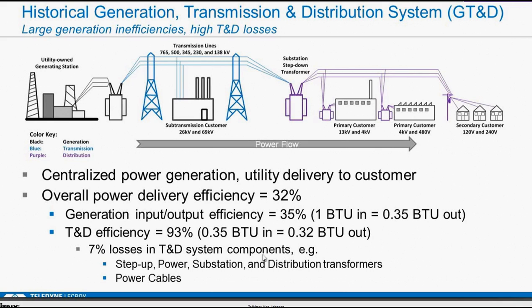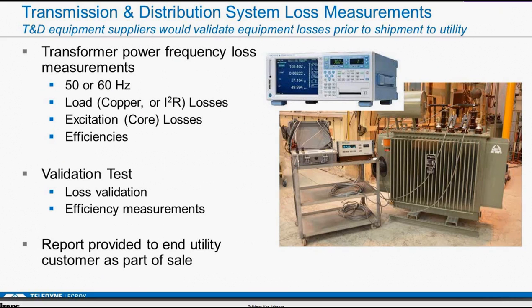So utilities historically wanted to measure losses in the step up, the power, the substation, and the distribution transformers, and also in power cables and other associated equipment. So historically, someone who made these types of devices and supplied them to utilities would test this transformer with something called a power analyzer, and they'd measure the load losses and the core losses or the no load or excitation losses of a transformer, and it would calculate efficiency. It was done kind of as a final validation test to give the utility a report that they were getting what they purchased, in terms of efficiency on the transformer.